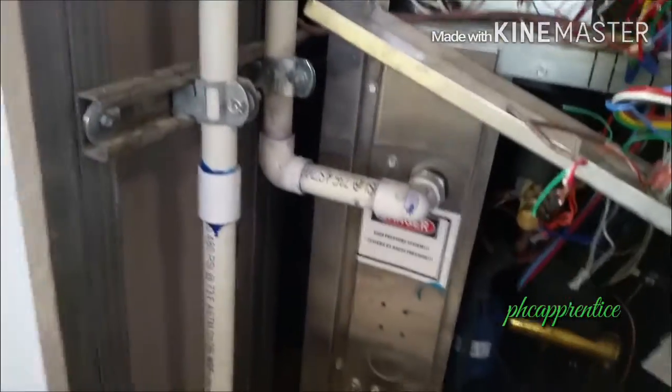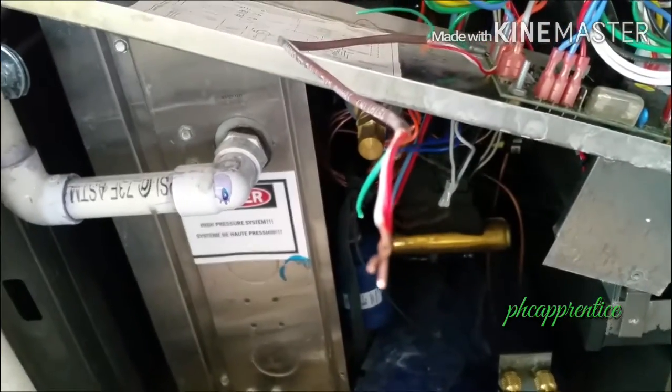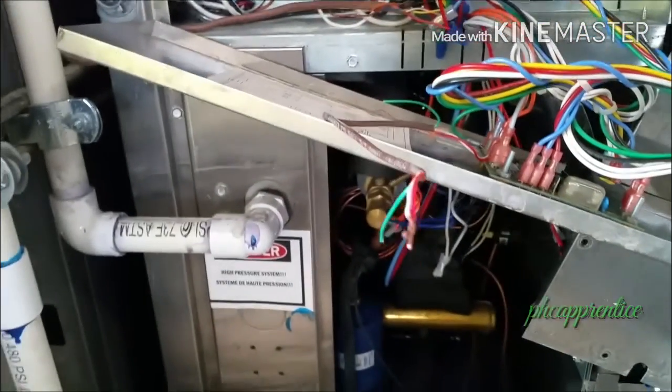The engineer thinks the pipes may have been reversed. What I did is put a bypass on the pressure switch. I'm going to disconnect the bypass in about two minutes and see if everything stays stable.